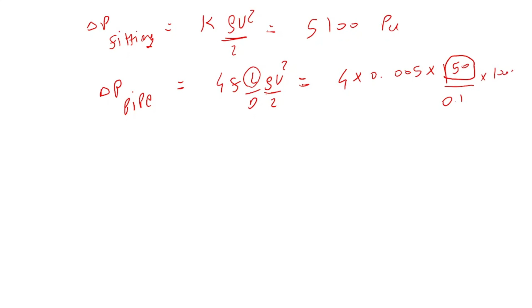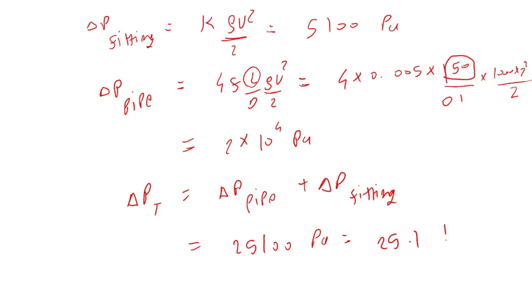So this is 0.005. See, this is important. Now you are using the K method, so this is the actual pipe length by 0.1, 1000, 2 square by 2. Okay, so our value is somewhere around, I think, 2 into 10 to the power 4 Pascal. So your total pressure drop delta P total will be delta P due to pipe plus pressure drop due to fitting, and this is somewhere around 25100 Pascal, so 25.1 kilopascal, right? So one value we got from the K method.